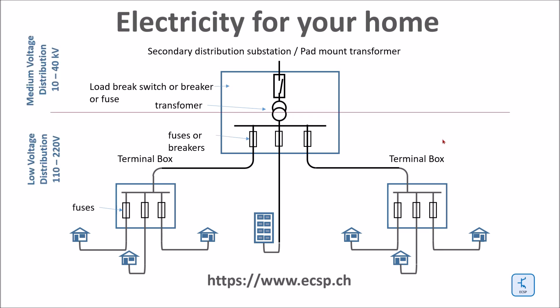In larger cities there are hundreds of terminal boxes. They are bundled and connected to secondary substations. Larger houses may be directly connected to the secondary substation. The secondary substation connects the low-voltage distribution grid to the medium-voltage distribution grid. Therefore there is a transformer, some low-voltage fuses or breakers, and a medium-voltage load-break switch or high-voltage breaker. The secondary substation builds the bridge between the low-voltage distribution of a couple of hundred volts up to the medium-voltage distribution between 10 and 40 kilovolts.